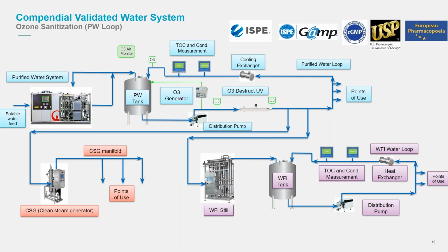This one's showing ozonation. So you ozonate the main tank and use an ozone UV destruct to remove the ozone before it gets to the point of use. When you want to sanitize, you turn the UV off, so the ozone now goes through the whole ring main, and you kill off any bacteria using ozone. The ozone is generated through an electrolytical system here, which actually splits the water using electricity. So there's no added chemicals into the system, which is, again, as part of the ISPE guideline, it's better, or preferential, that we don't add any chemicals into the system.